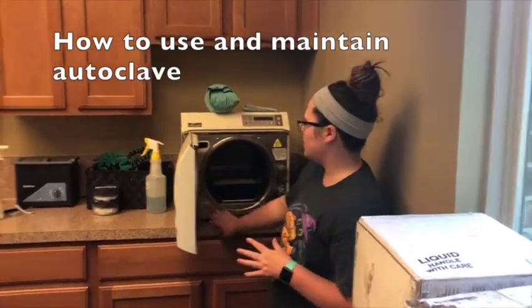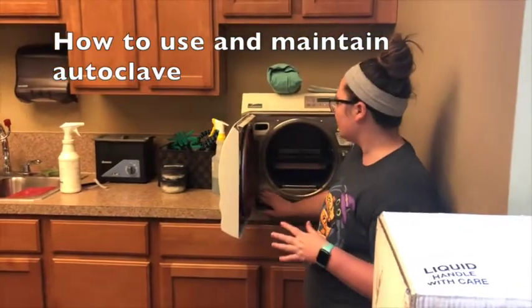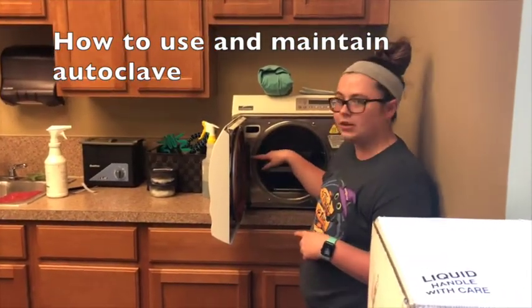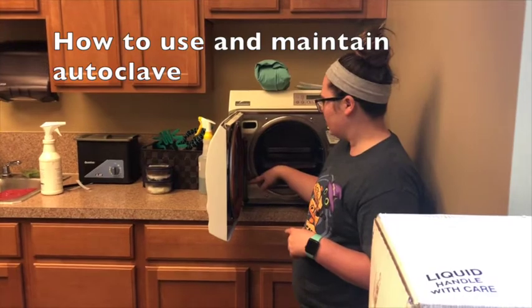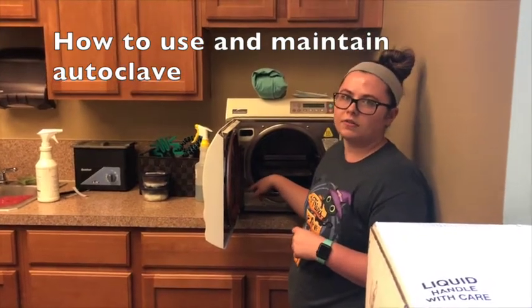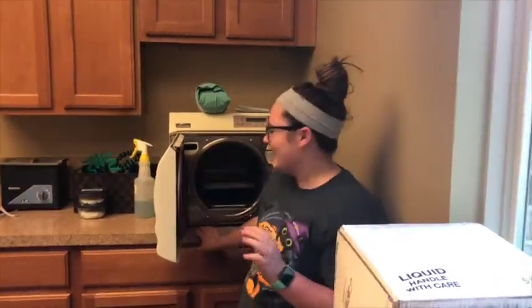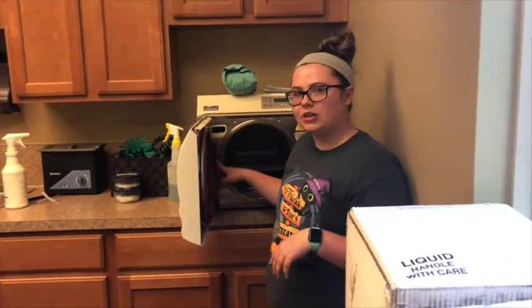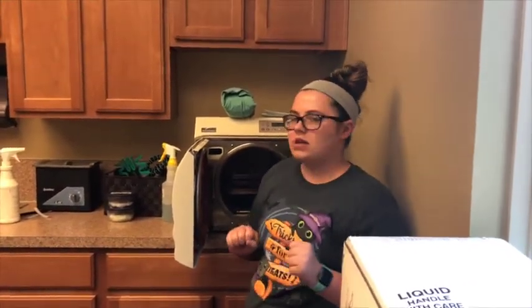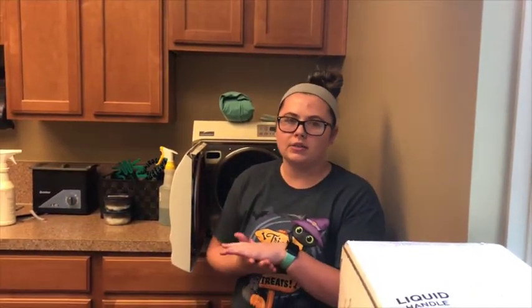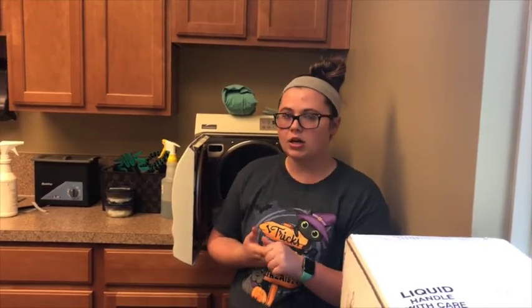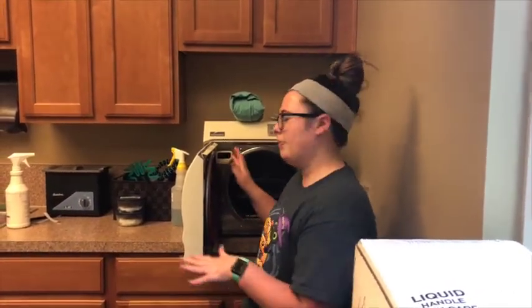So there's an insert right over here on the side where the water goes, and you want to make sure the water is in the green. The water's too low if it's in the red. Your packs will not become sterile if it's in the red. So you want to make sure you have enough, so our water's in the green, not the red. And then we use deionized water. Some autoclaves take distilled water. So we've already made sure this is set up.